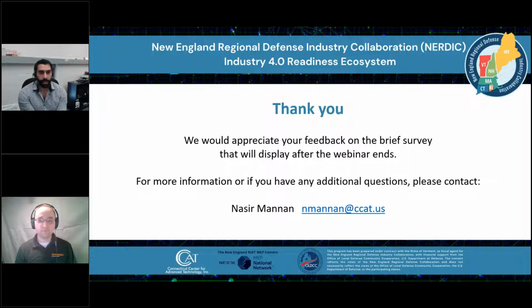What would be a typical process for onboarding machine probing, if a company was interested in adopting this technology? A typical retrofit involves having a representative from Renishaw come to your facility for installation. Our engineers install the probe, wire the receiver to the machine, commission and calibrate it, and that includes 1 to 2 days of training. If you're using Inspection Plus or GoProbe cycles, we'll walk you through how to use those. If you have a specific application, we can assist with getting started. Generally the whole process is 1 to 3 days, depending on how quick the install goes and how much training you require.